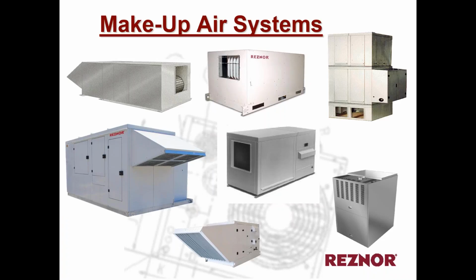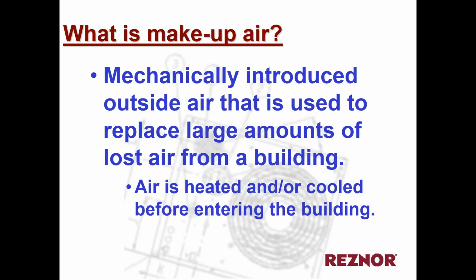Now, make-up air systems are a keystone of what Reznor does. In fact, Reznor back in the 50s essentially invented make-up air. Make-up air is mechanically introduced air that makes up for, say, an exhaust fan or some other apparatus that's pulling air out of a building. Once we make that air up, we also have to treat it. We either have to heat it or cool it before it enters the building so as to not tax the comfort heating or cooling products that are already doing the job in the space.